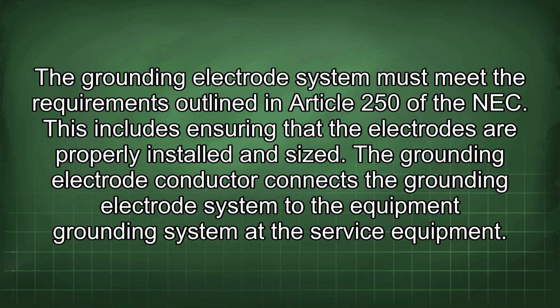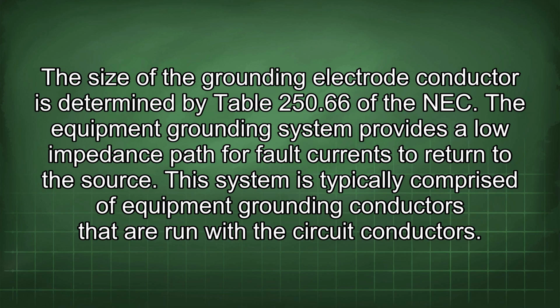The grounding electrode conductor connects the grounding electrode system to the equipment grounding system at the service equipment. The size of the grounding electrode conductor is determined by Table 250.66 of the NEC. The equipment grounding system provides a low impedance path for fault currents to return to the source. This system is typically comprised of equipment grounding conductors that are run with the circuit conductors.